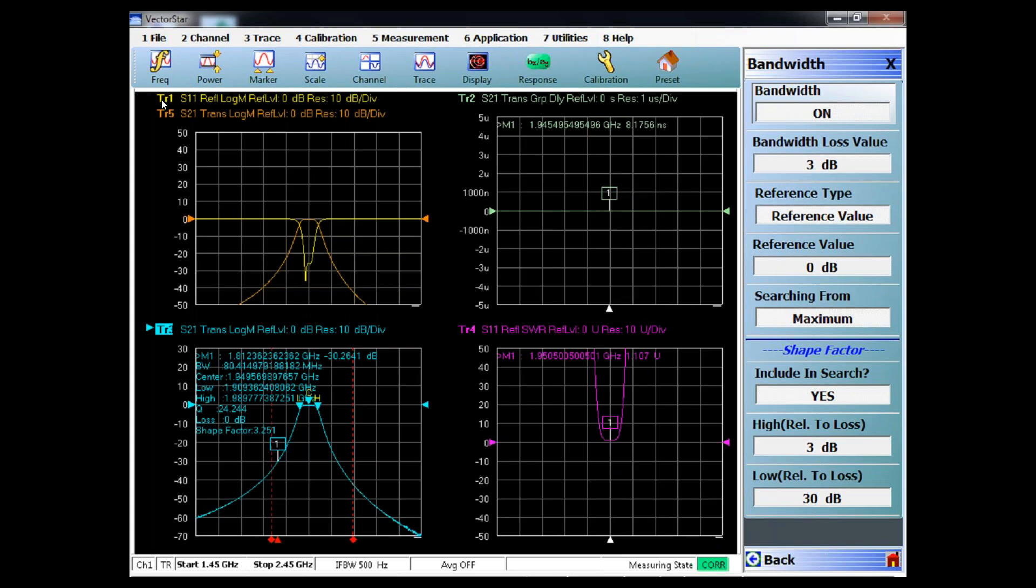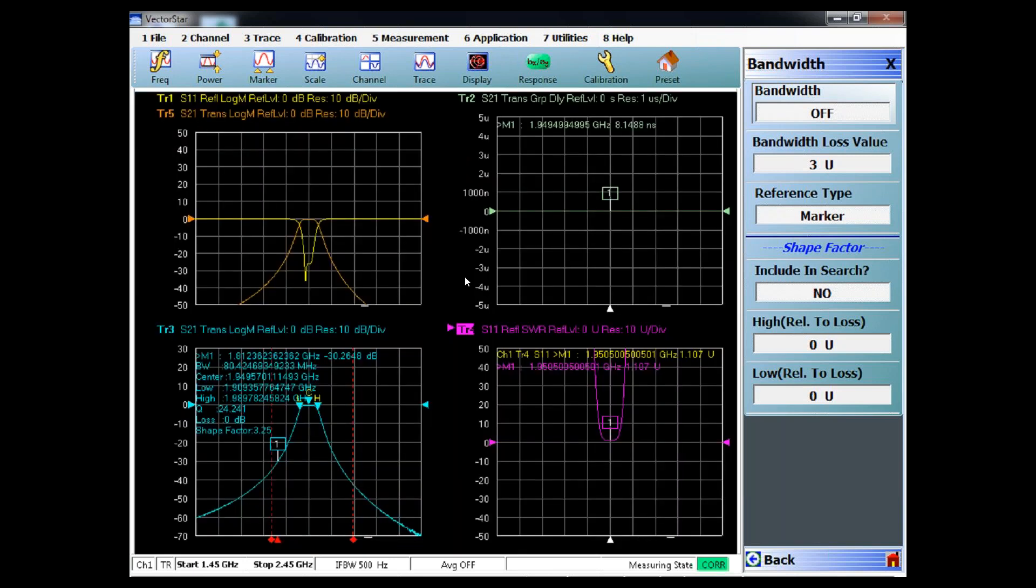Another common measurement for a filter is group delay. You'd move your marker to the frequency where it functions, and you can see that our group delay is 8.1 nanoseconds. Another common measurement is VSWR, and within the pass band, you'll have a specification. In our case, this is 1.107.